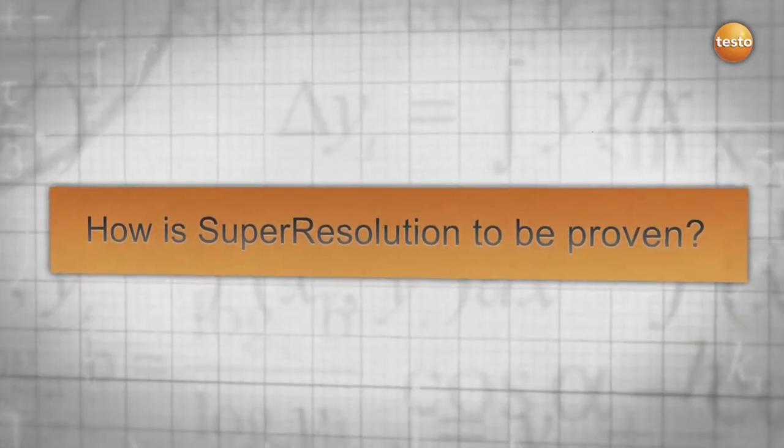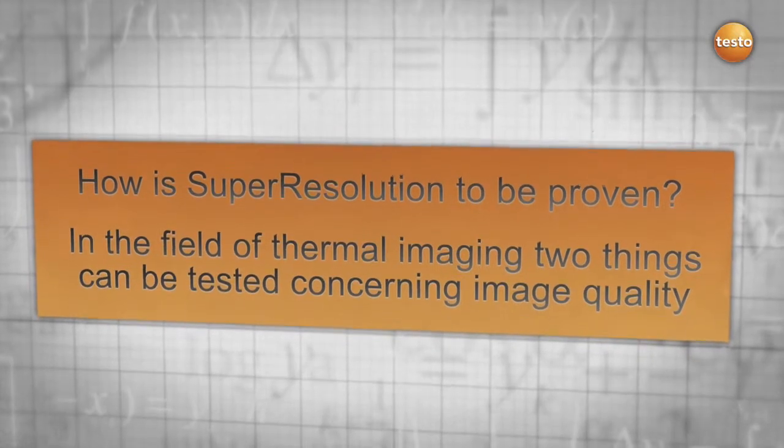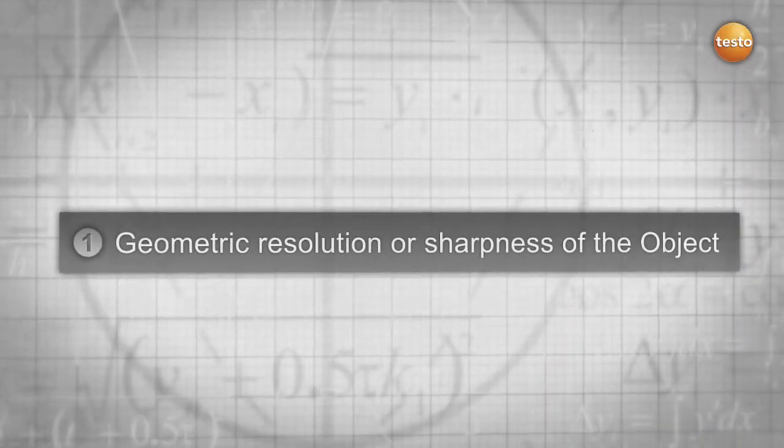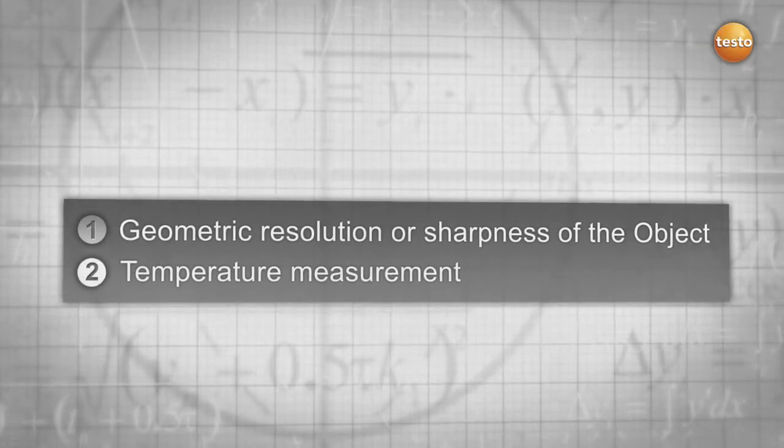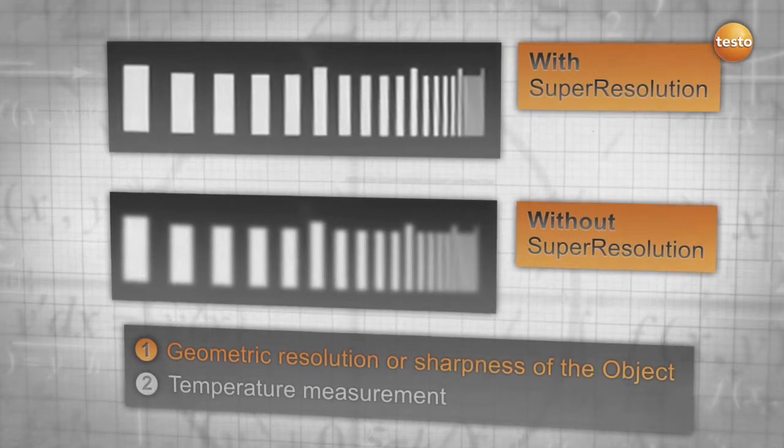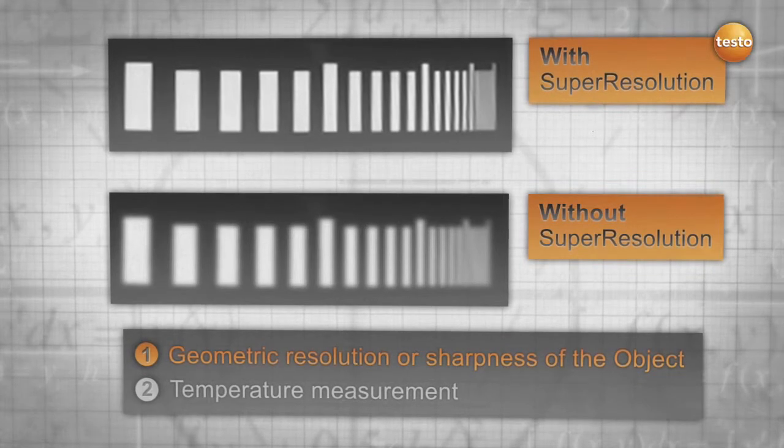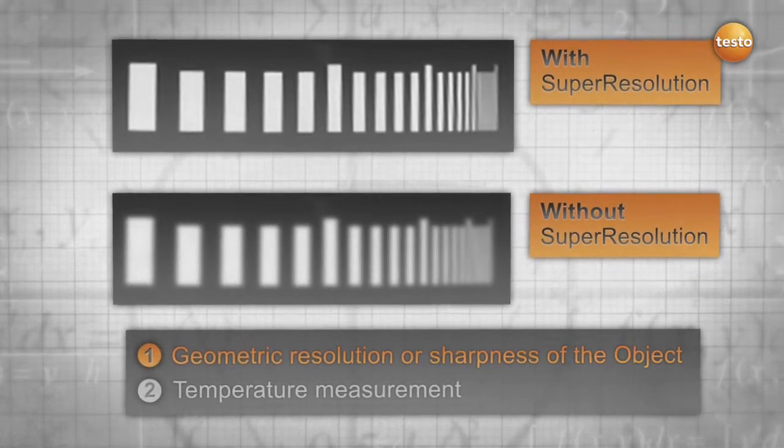But how can super-resolution be proven? In the field of thermal imaging, there are two factors that play an important role in the quality. These are geometric resolution, or sharpness of the object, and precision of the temperature measurement. The difference is clearly seen in this test. A gobo with vertical slots of different widths and distances is placed in front of a black body that has a certain temperature.